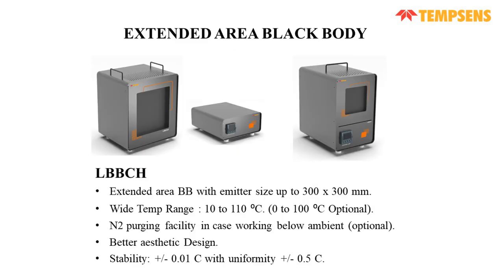Then we have the extended area Blackbody LBBCH. The range for the LBBCH models will be 10 to 110, and it can be optional from 0 to 100°. It also comes with a nitrogen purging facility, and stability is plus minus 0.01 and uniformity is plus minus 0.5 centigrade. These models are available up to 300 by 300 mm or up to 500 by 500 mm as well.